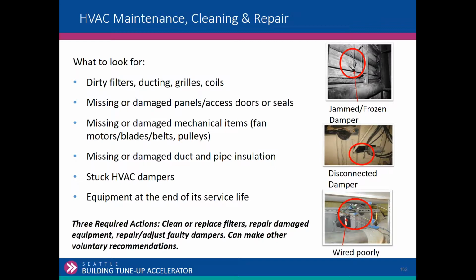What's optional is that if the equipment is at the end of its service life, it should be replaced, then you should make that recommendation, but they don't have to do that. That's not part of the scope in the tune-up project. If there's stuck dampers that are critical to the situation, those need to be fixed. That's part of the deficiencies. But replacing the equipment is not a requirement. It's voluntary. But dirty filters, that type of thing, need to be replaced as part of the tune-up assessment.